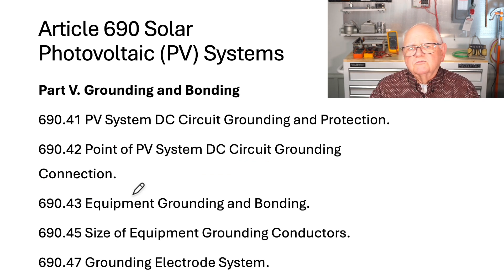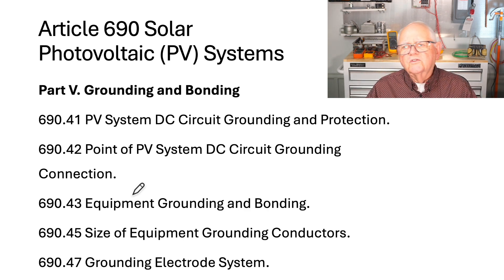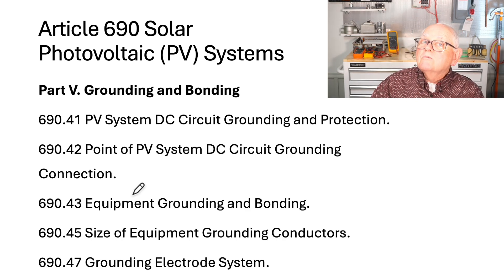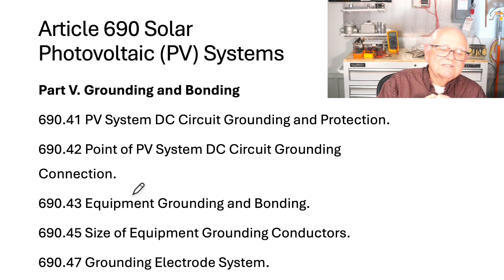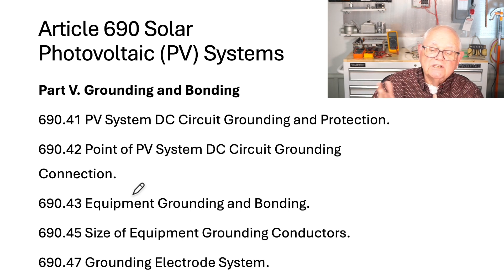Article 690 is on solar PV systems, and it's a separately derived system. You take DC power from a solar array, put it through an inverter, change the DC into AC, and take that AC out to loads or the grid. If you look in Part 5 of Article 690, you'll find five requirements for grounding and bonding of PV systems: 690.41 on DC circuit grounding and protection, and 690.42 on the point of DC circuit grounding connection; 690.43 on equipment grounding and bonding; 690.45 on sizing equipment grounding conductors; and 690.47 on the grounding electrode system.